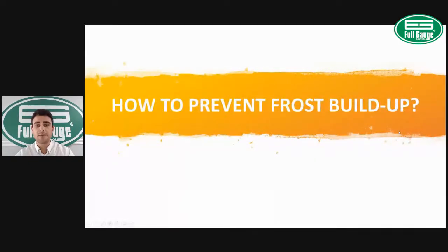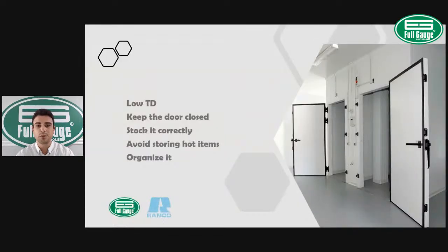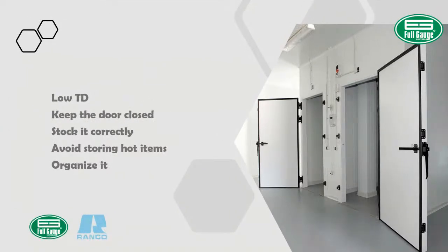So here we have a few tips on how to prevent frost buildup. First of all, frost is frozen water vapor. Ice forms when frost melts into water and the water freezes. The colder the evaporator, the more water vapor will freeze out of the air.